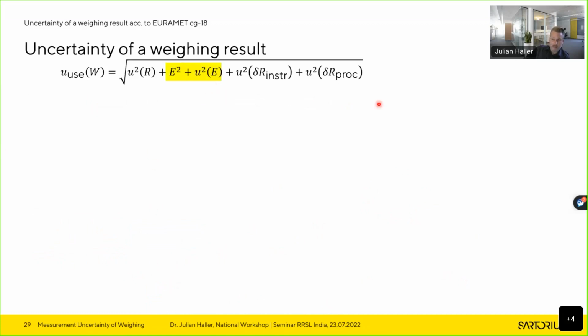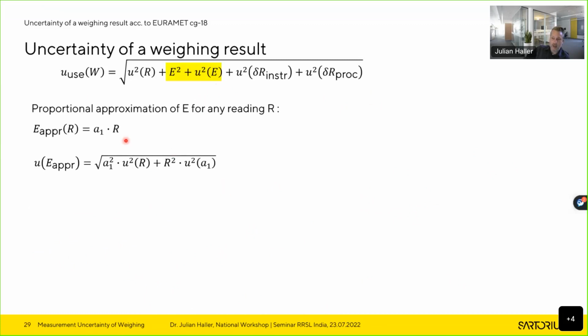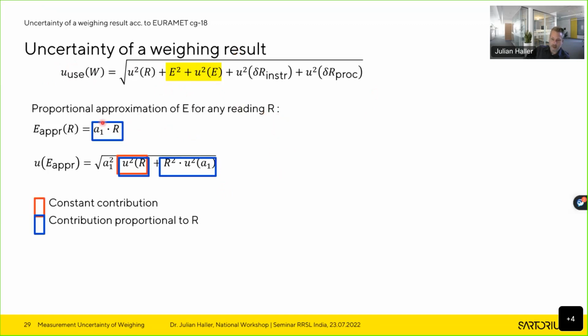Next contribution, as mentioned, is more or less the calibration result. So what we have to do now, if we want to calculate the uncertainty for any weighing result, is interpolate the results of the calibration. That is done like this. I'm not going into details of the formulas, don't worry. But again, you have constant contributions and contributions proportional to the reading or to the load.